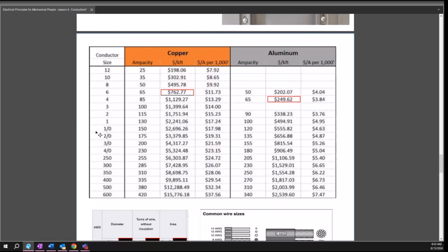Apart from a client potentially having in their specs or standards that you have to use copper and they don't accept aluminum for their projects, is there anything else that would make you have to use copper over aluminum, where you don't have a choice? The NEC does not allow aluminum in certain hospital situations. It requires copper in certain installs inside hospitals, and that's for reasons that.